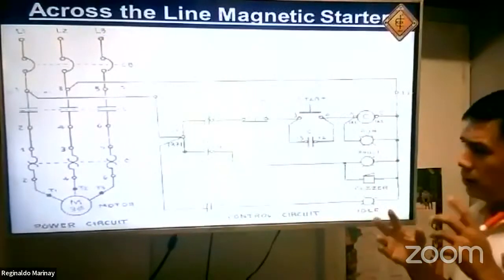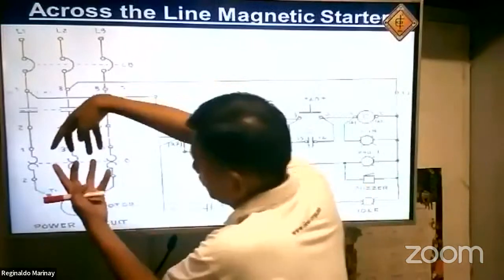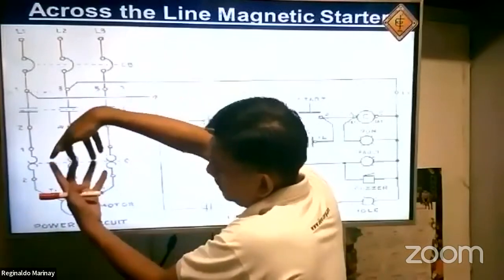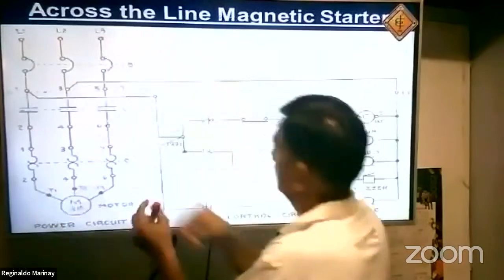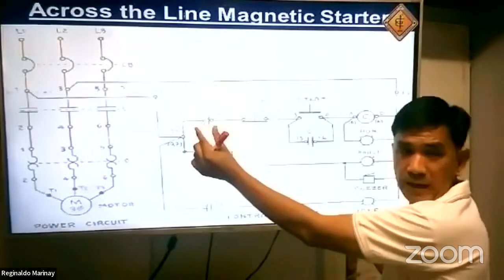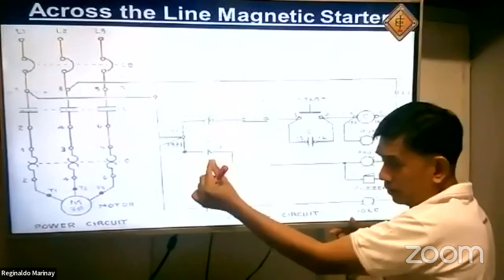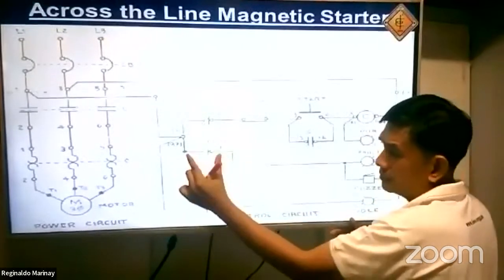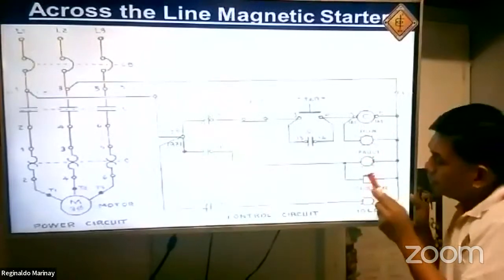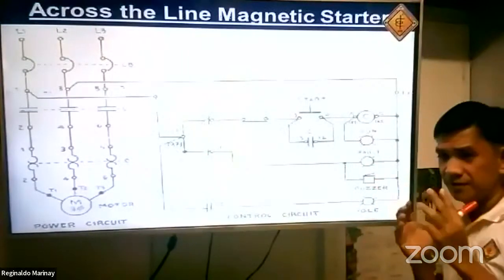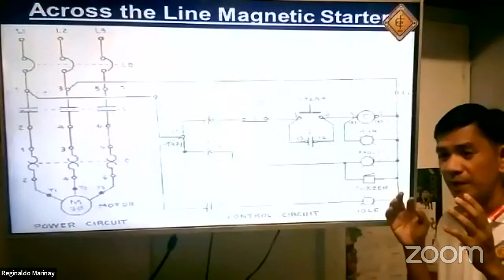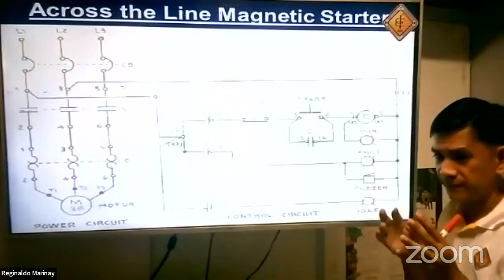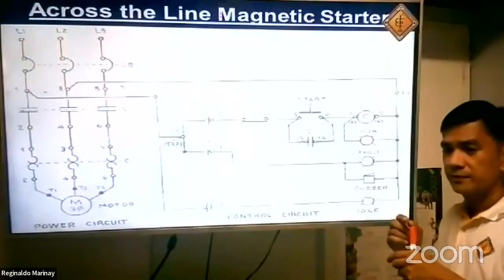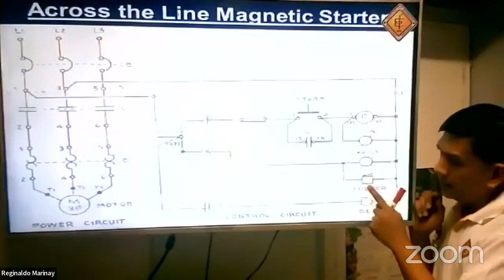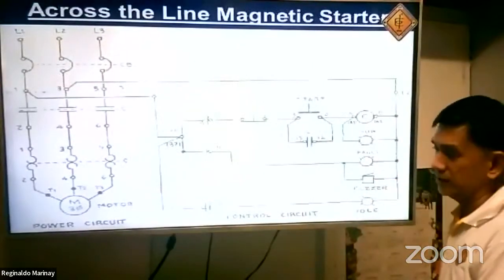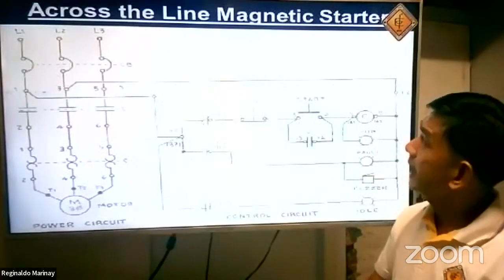It's running condition. Now, what happens if your motor becomes overloaded? If it becomes overloaded, the overload heater element will become open. Pop. If that becomes open, the overload contact here, 95 and 96, will become open. And this will become closed. At the same time, this will become closed. Because your motor becomes overloaded, 97 and 98 becomes closed, the current will flow here, energizing your fault lamp and your buzzer. Once you hear your buzzer, pag tumunog yung buzzer mo, meaning there is a fault. See, there is a fault on your motor. There is an overload condition with respect to your motor. That is the idea.